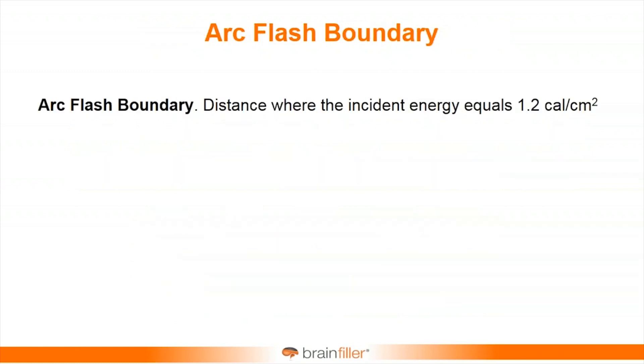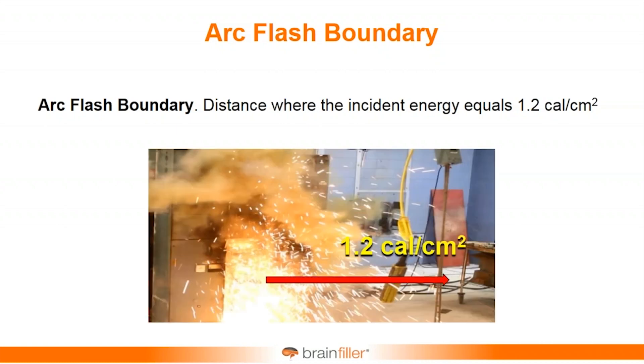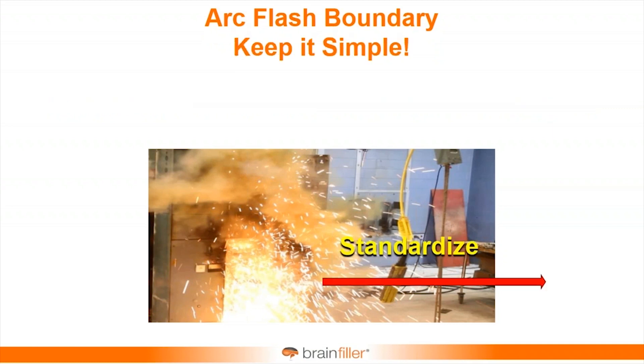For this method, one of the first things I look at is the arc flash boundary. The arc flash boundary triggers where you have to put on your arc-rated PPE. But if you're going to be performing energized work, you're going to be doing that anyway. Other than that, the arc flash boundary is to keep unprotected people back a certain distance. So instead of having that distance at exactly 1.2 calories per square centimeter, maybe adopt a larger standardized arc flash boundary.